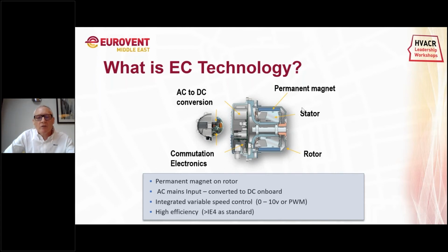Speed control has integrated variable speed built into the motor itself. From a control solution, you can control this from a 0 to 10 supply, 4 to 20 milliamps. The larger motors, and even some smaller motors now, come with Modbus control, so an RSA, RSB connection, and you can literally plug it straight into your BMS system.